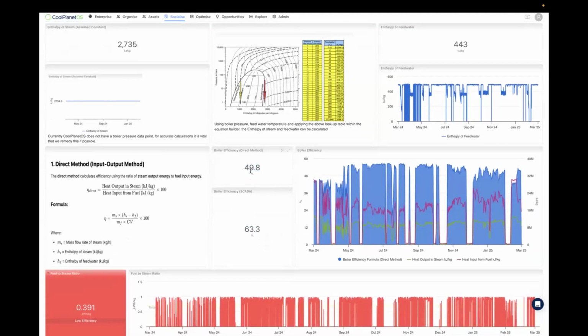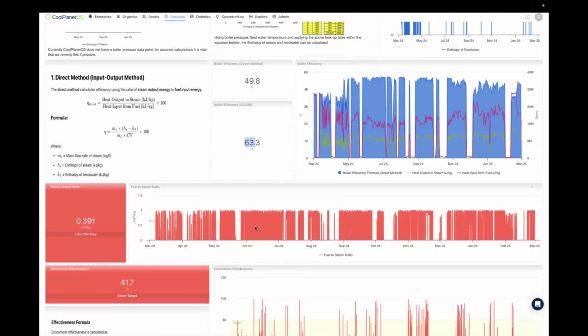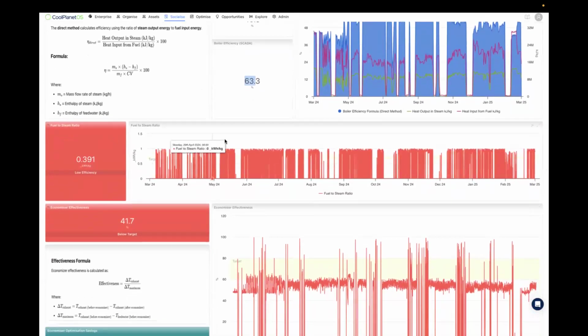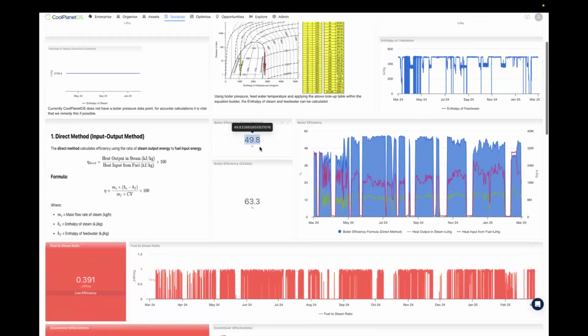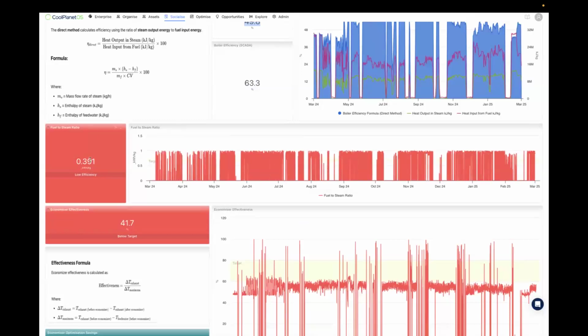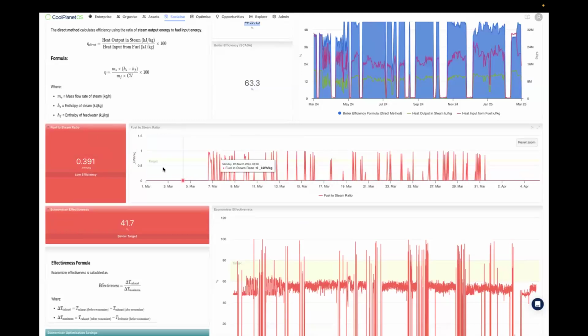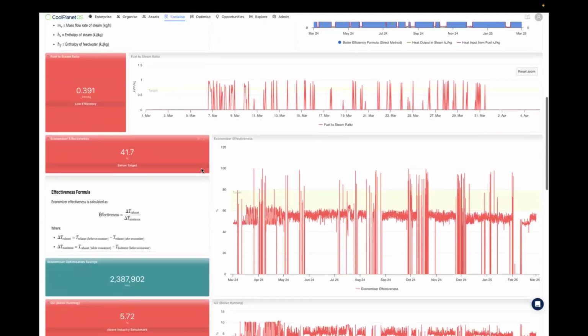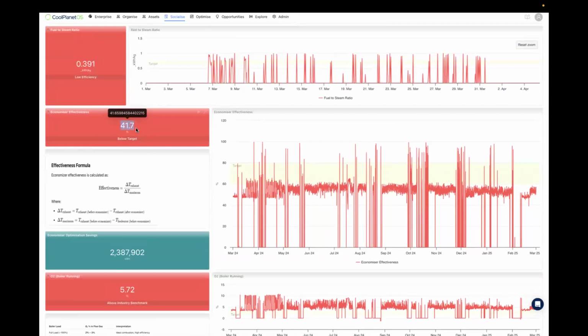As you can see here, this is quite low versus what's been displayed on the SCADA, even though the SCADA output is also quite low. And then we're drilling down into different KPIs that validate that efficiency output. So fuel to steam ratio, you can see it's well below industry target for this size of boiler and this type of boiler. We're looking at the economizer effectiveness. Again, it's way below target versus industry standard for this particular boiler.